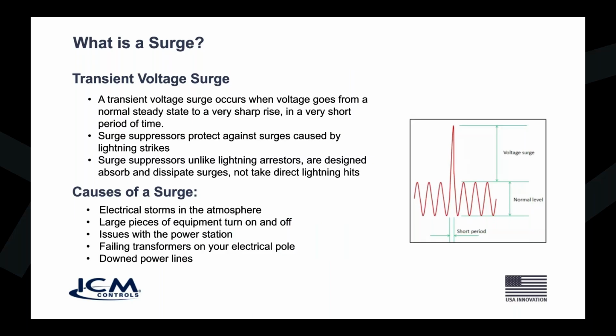And specifically, I want to clarify something. Surge suppressors, SPDs, are designed to protect against surges caused by lightning, but not a lightning strike itself. A direct lightning strike, not much survives that, right? Direct lightning strike will split oak trees in half. It'll melt things right, to molten, lead, turn sand into glass.